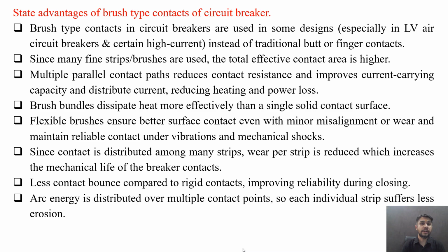Advantages of brush type contacts of circuit breaker. So there are several advantages. Some are listed here. Brush type contacts in a circuit breaker are used in some designs, especially in low voltage air circuit breakers and certain high current applications, instead of traditional butt or finger type contacts. Since many fine strips or brushes are used, the total effective contact area is higher. Multiple parallel contact paths reduce contact resistance, improve current carrying capacity, distribute the current and reduce heating and power losses. Brush bundles dissipate heat more effectively than a single solid contact surface.